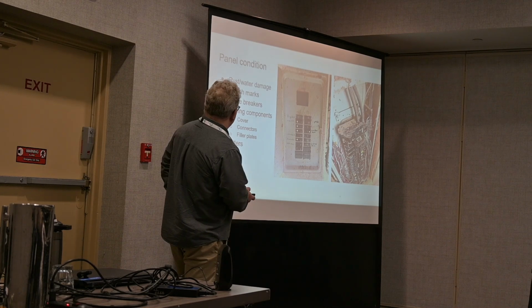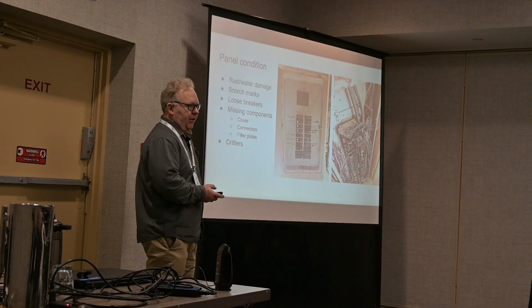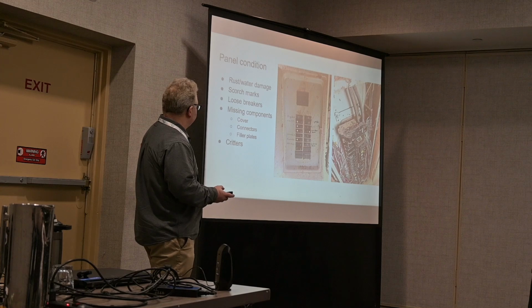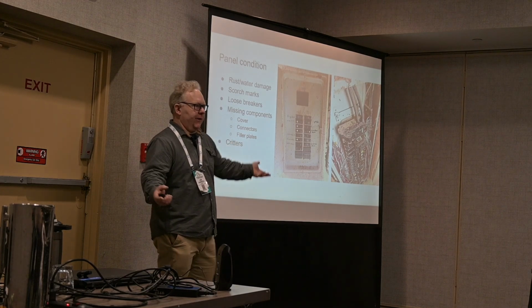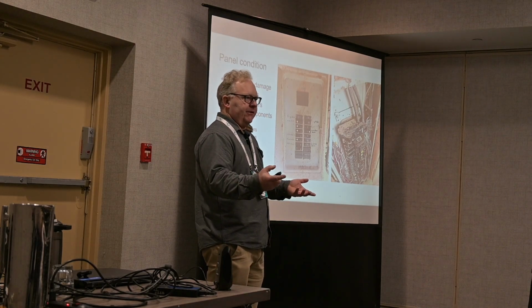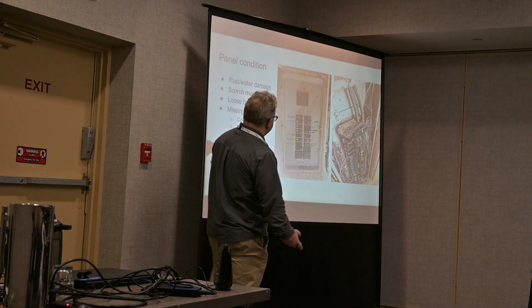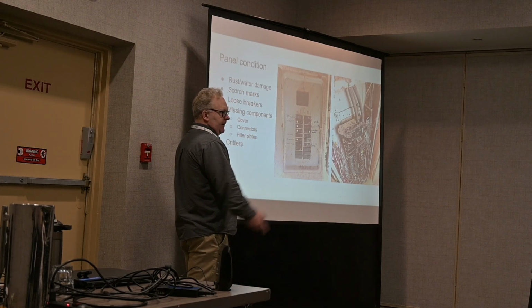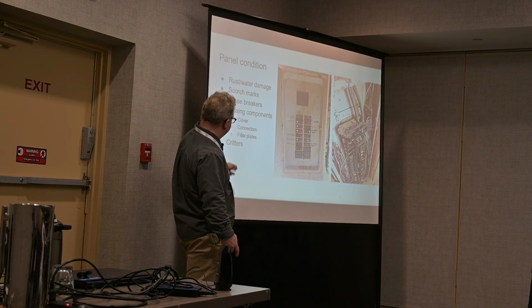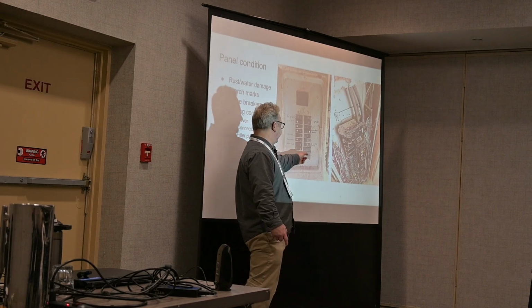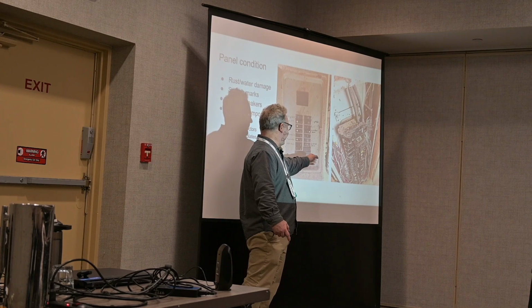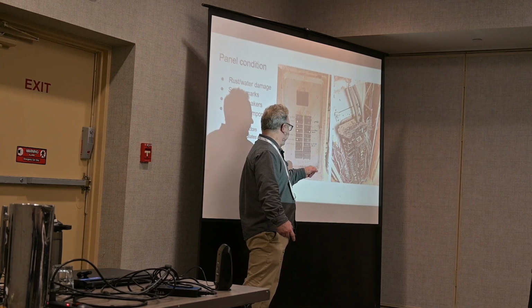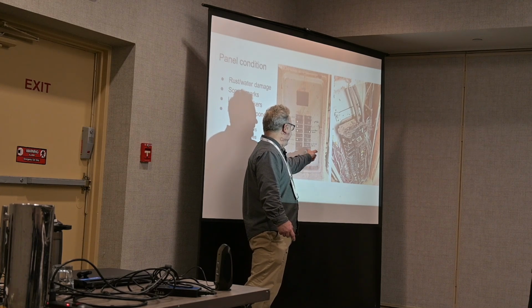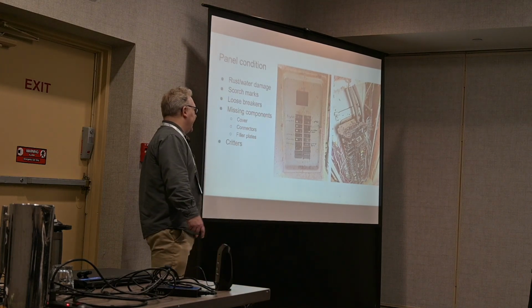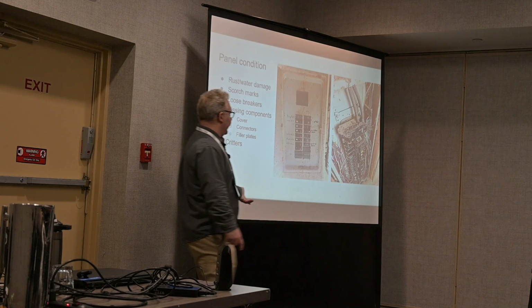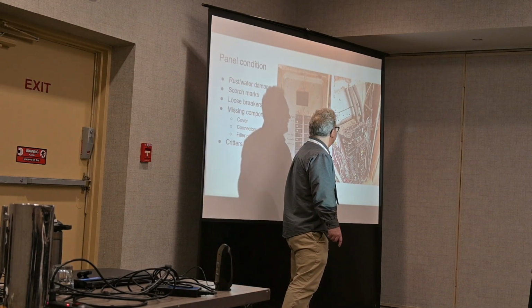We want to take a look at the panel condition. Is there rust? Are there scorch marks where there might have been some kind of damage? Are there loose breakers? Is stuff missing? I mean, we go into houses where the panel cover is missing, and it's kind of terrifying because there might be kids playing in that basement. But also things like the connectors that prevent the wires coming into the panel from shorting out, and missing filler plates. So oftentimes people will pull out a circuit breaker and leave that opening empty so that a person could potentially reach in and touch the live conductors. This one has filler plates, which is good, but that's another thing to look at. And just being aware of potential rodent damage, things like that can happen in a panel.